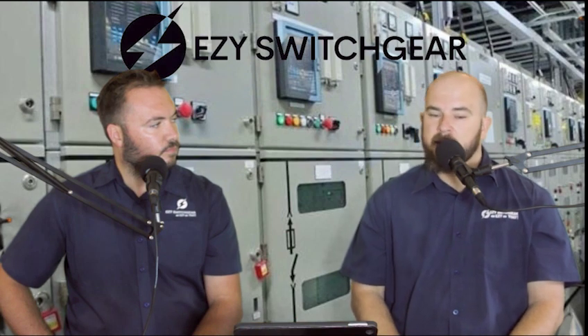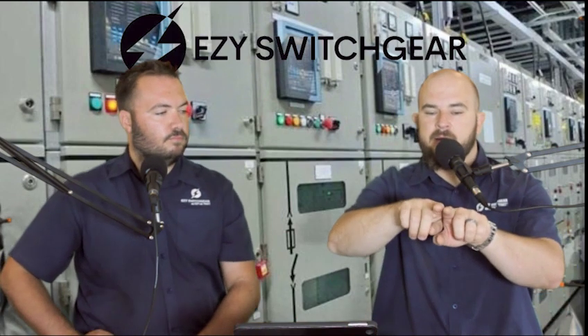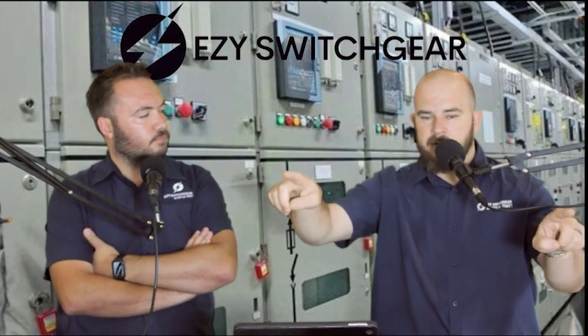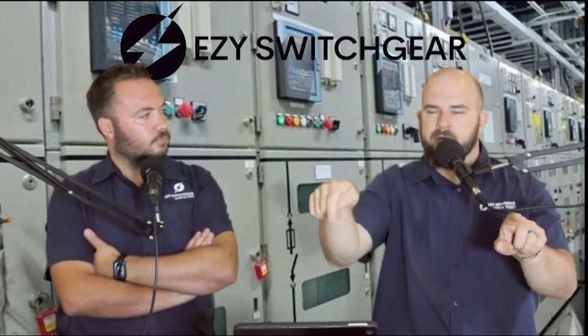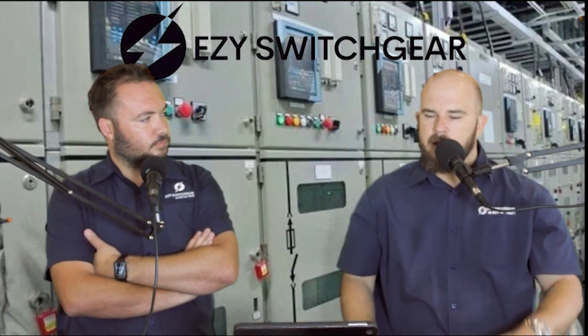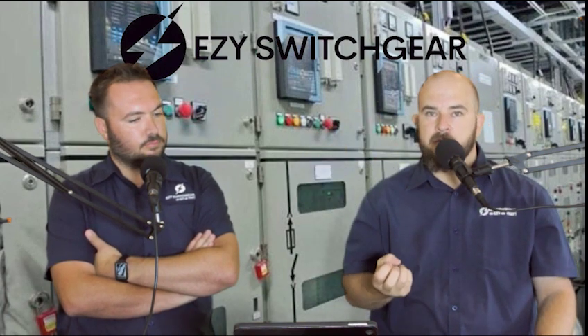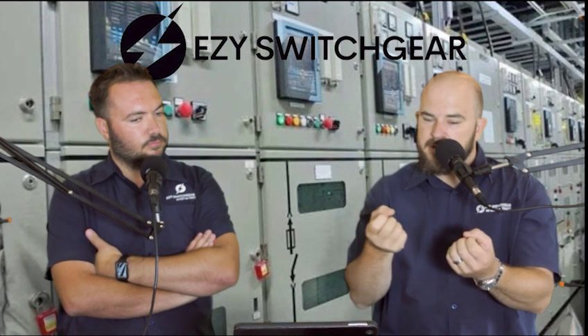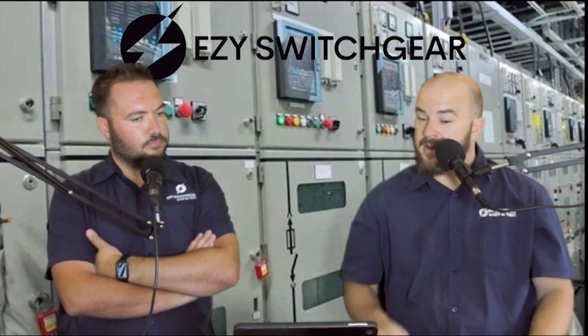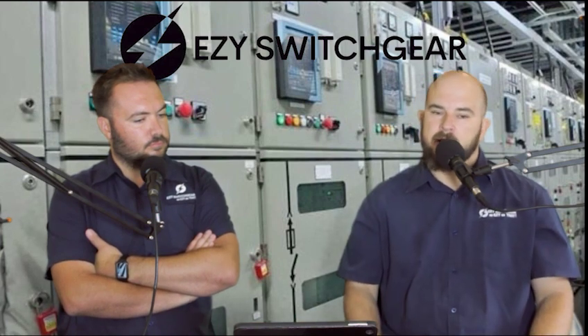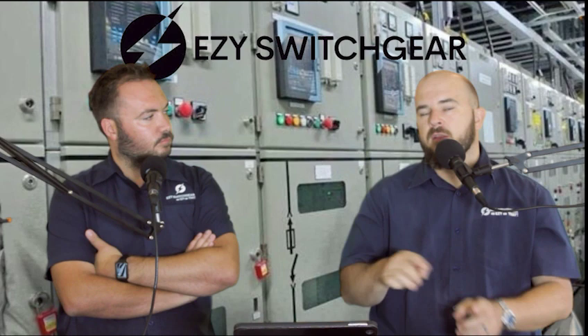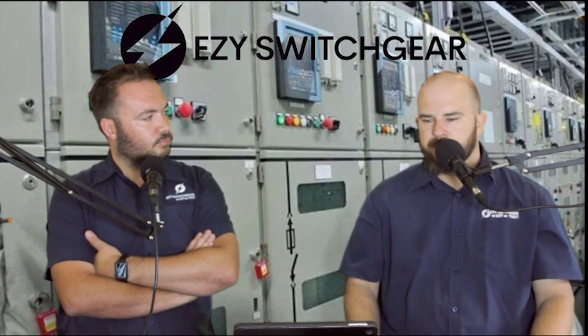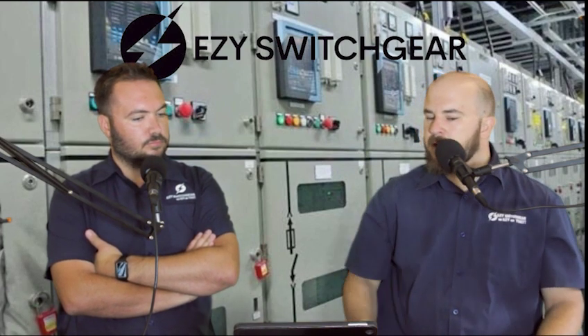In switchgear we have different kinds of insulation. We have air insulated switchgear, which literally means they're just spacing it, giving it space in between so it cannot jump between phases or phase to earth. Then you have gas insulated switchgear, where instead of plastic and other insulating materials, you're using a gas, and that is quite interesting. Then you have solidly insulated switchgear, where you use epoxy or other methods. And then oil insulated switchgear, where you use oil to prevent the voltage from jumping through. So the first one that we're going to speak about is air insulated.